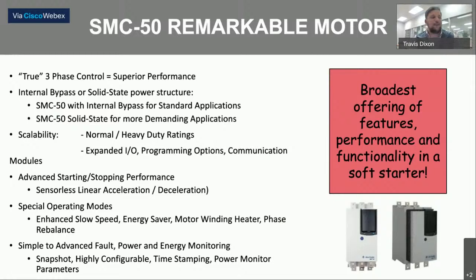So just to wrap things up, true 3-phase control that equals superior performance. Also, the simple to advanced fault power monitoring, that's a key factor in the SMC 50. The ability to see your diagnostics accuracy and time stamping, snapshots of what's happened with your SMC, is highly configurable.